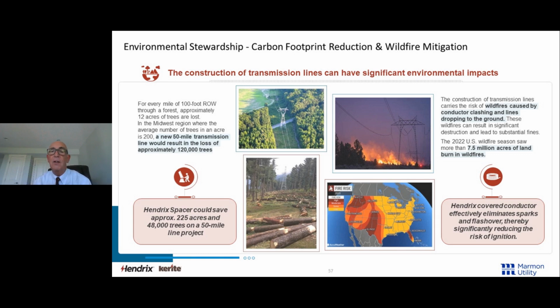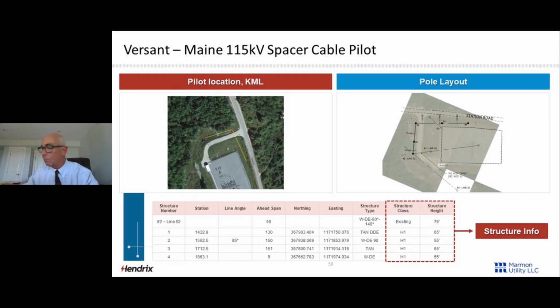And if you take a look on the right, the construction of a transmission line carries the risk of wildfires caused by conductor clashing and lines dropping to the ground. We only have to look at the news during wildfire season to understand that this is real. In 2022, the U.S. wildfire season saw more than 7.5 million acres of land burned in wildfires. And Hendrix covered conductor effectively eliminates sparks and flashover, thereby significantly reducing the risk of wildfire ignition.